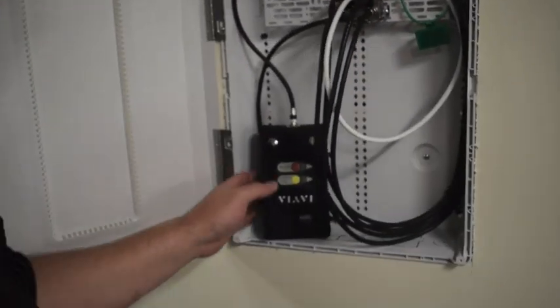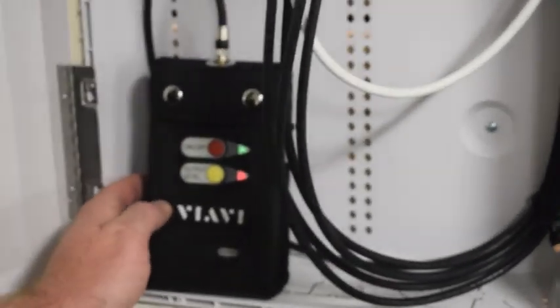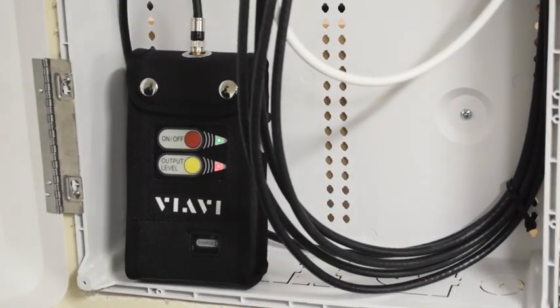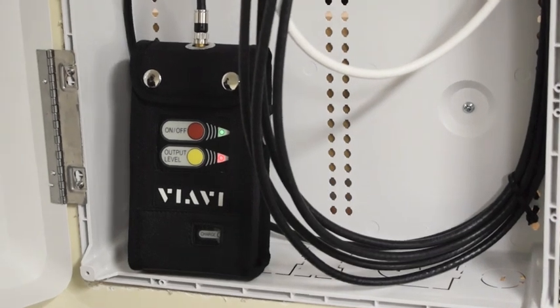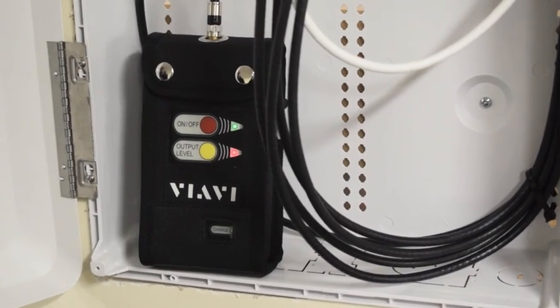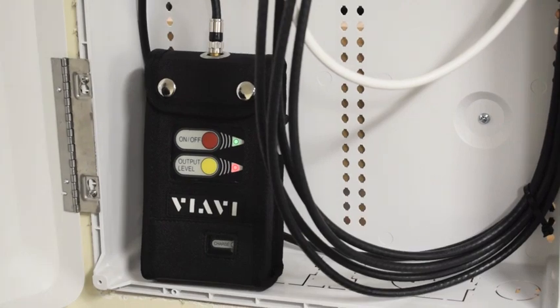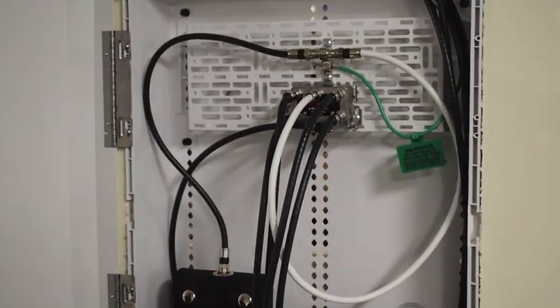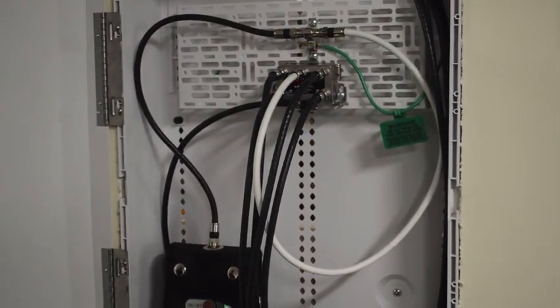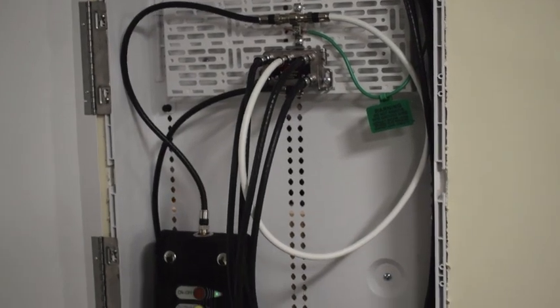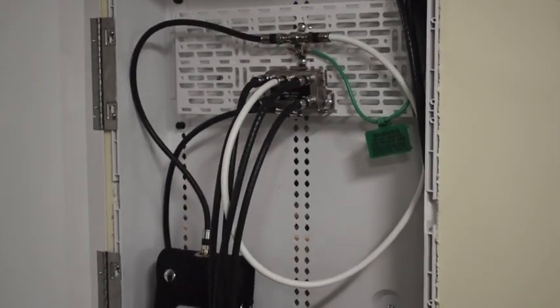We're going to turn our transmitter on. Green light on the transmitter indicates you have a good battery level. Output level with a red light indicates that it's at its highest setting. We're going to leave this on its highest setting. General reminder, please don't use the red jumper that comes in your kit, or may come in your kit, as that's going to also cause some leakage.